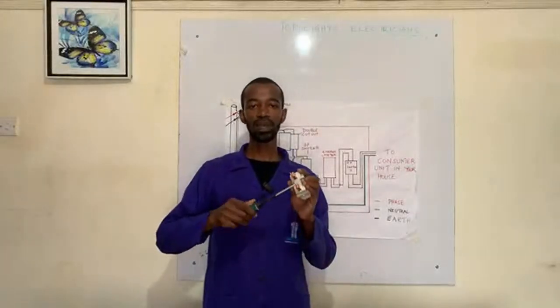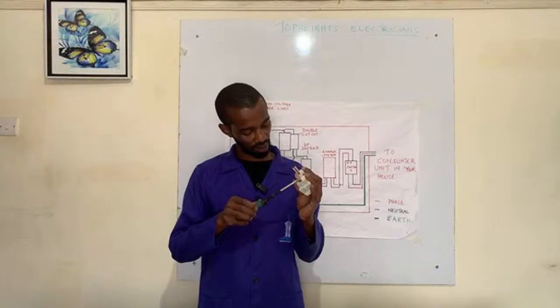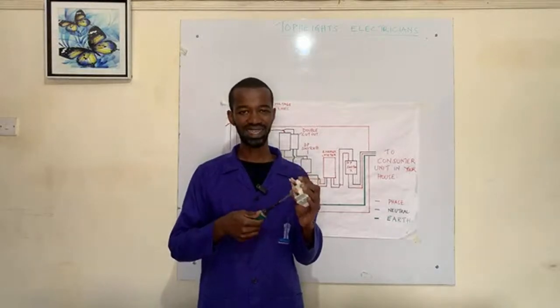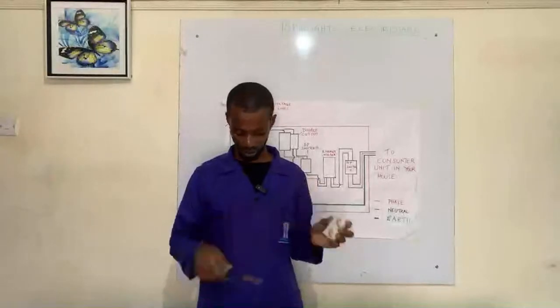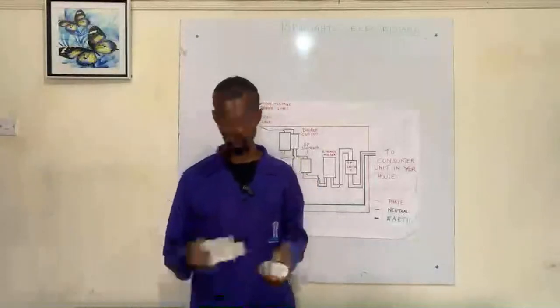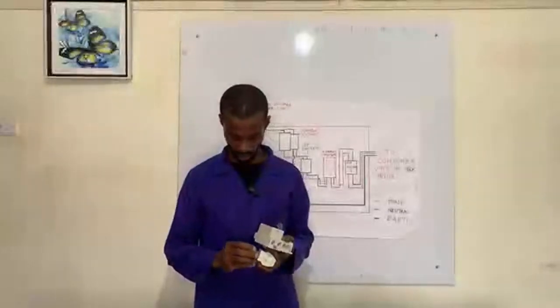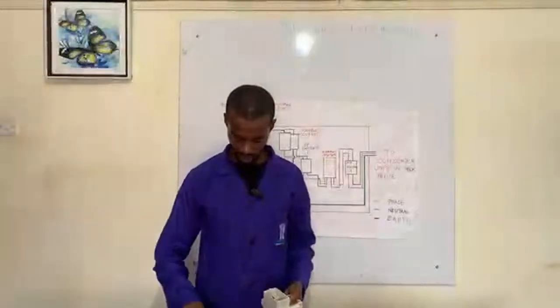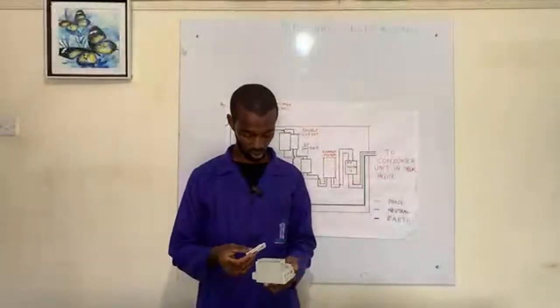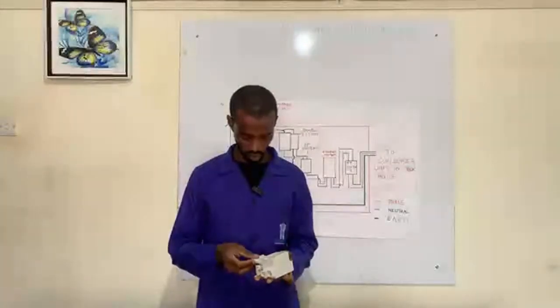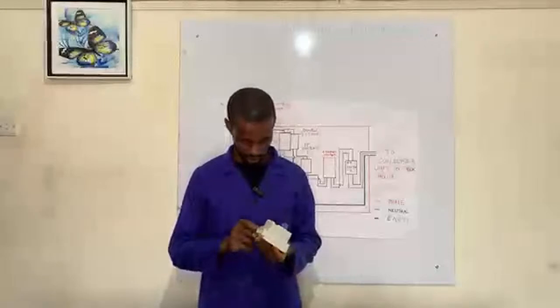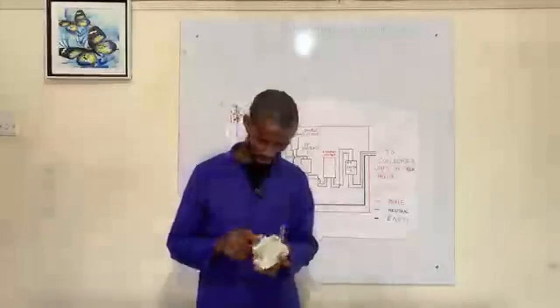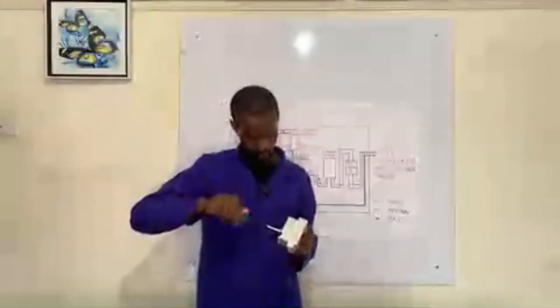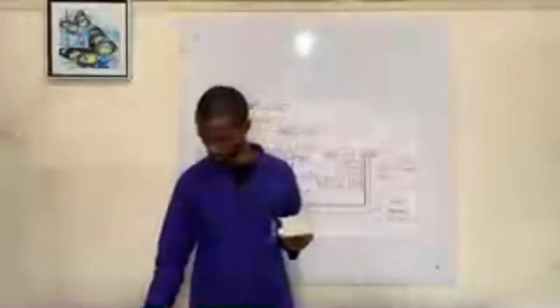A tester will not make a good connection there because you will not be able to tighten that screw. So it means that connection will be loose, right? And we don't want that in our electrical connection. We don't want to create loose parts or come up with connections that are loose.